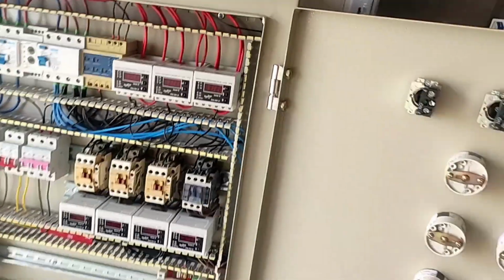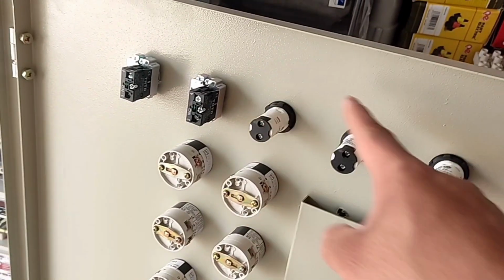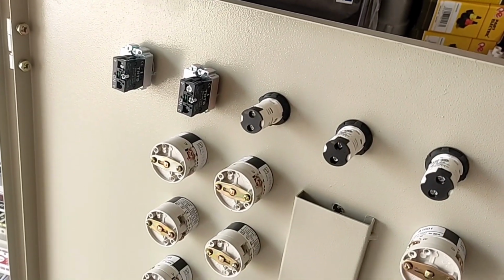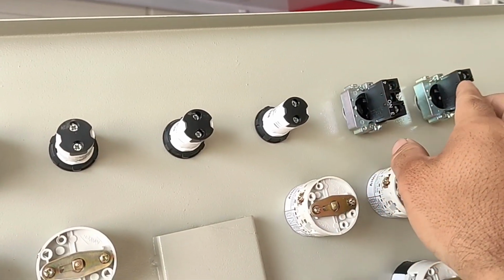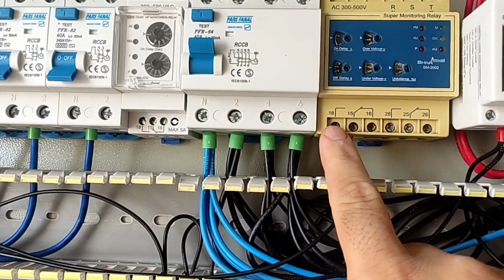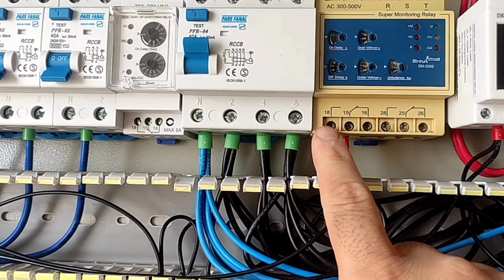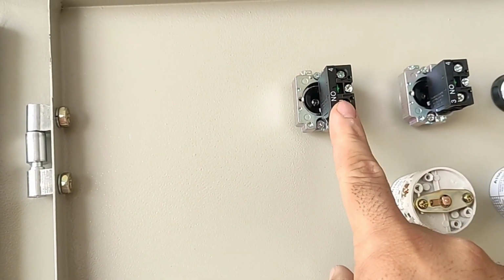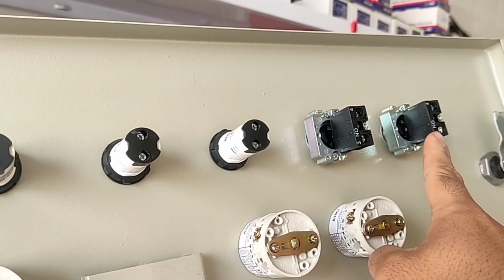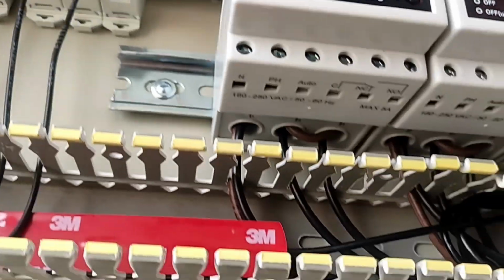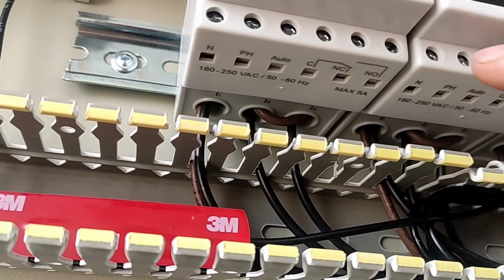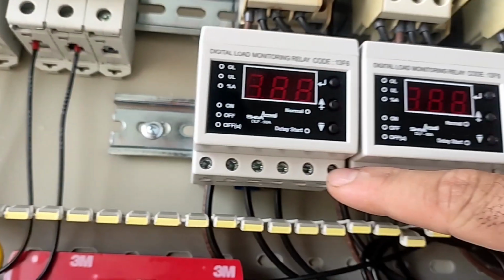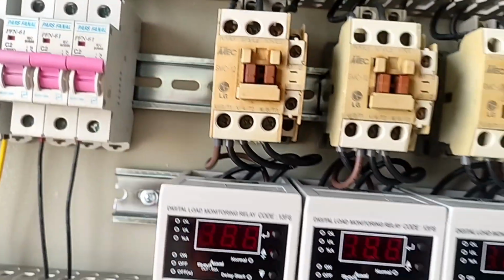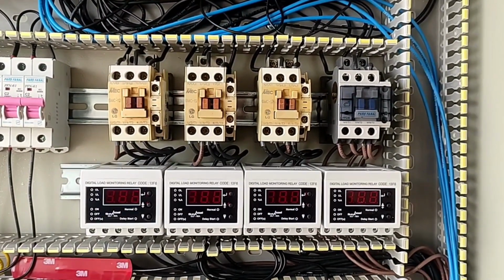There are also 3 signal lights installed on the door of the electrical panel, each of which is connected to one phase and their neutral is also common. To turn on and off the 3-phase outputs, 4 selector switches are used, whose input is connected to the output of the 3-phase monitoring relay, meaning pin 18, and the output of which is connected to the input of the current controller relay. And from the output of the current controller to its corresponding contactor coil. Now, according to the description, we do the wiring.